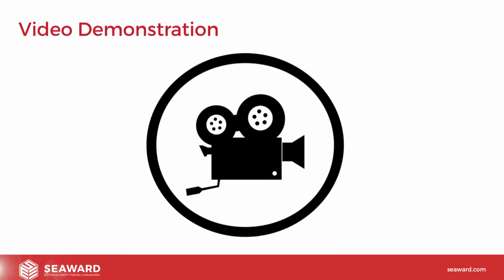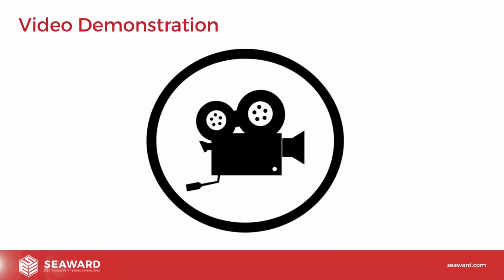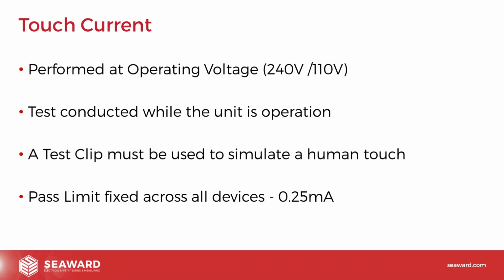Okay, so we've had a look now at the protective earth conductor current test. Let's have a quick look at the touch leakage test. So, similar to the protective earth conductor current, we're performing the test at operating voltage, so typically 240 or 110 volt operation. The test again is conducted while the equipment under test is in operation.